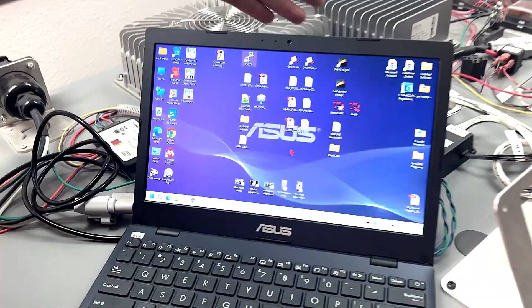You can see the one module that I replaced, the voltage was much higher. There are two ways that I can correct that, and it's close enough that I felt it was okay to plug in - that's about as far out as you'd want, though. So you can either connect a load, put a load on the battery, like I connected two 12-volt lights in series and put a load on the battery. It actually needed to bleed that down longer. Or, for the other three modules, I could bring those voltages up higher. But ideally, they should all be closer than this.